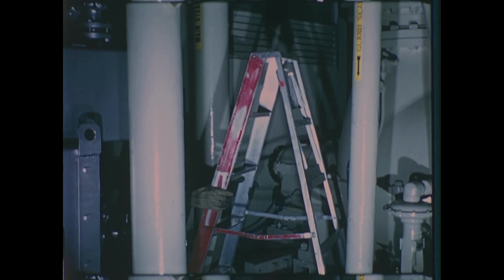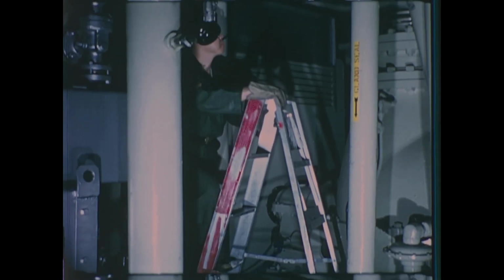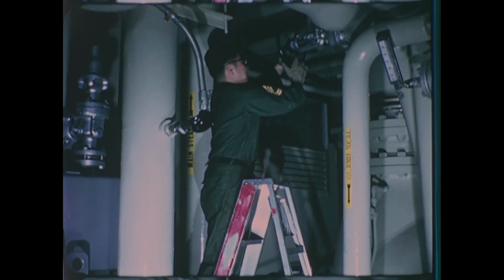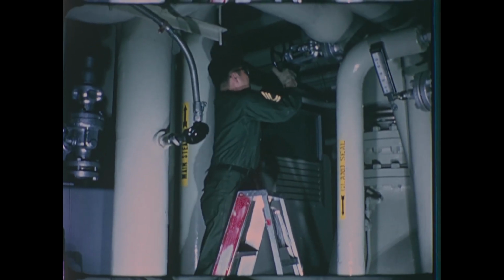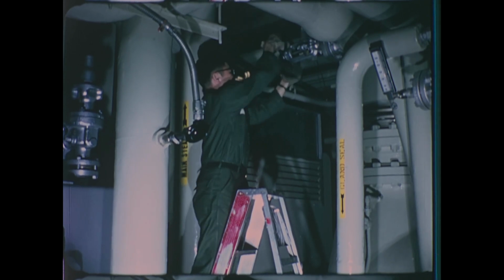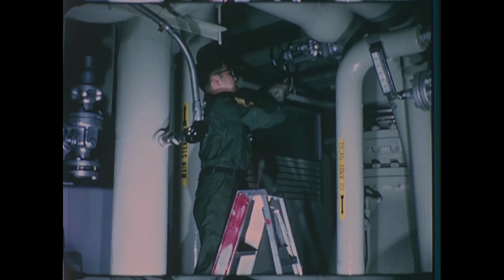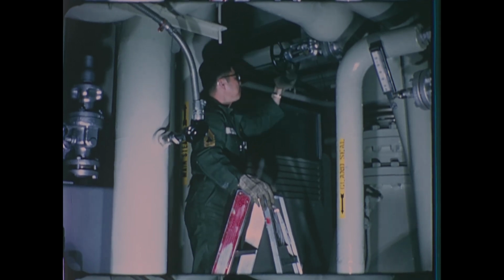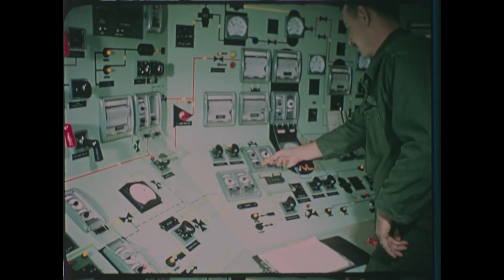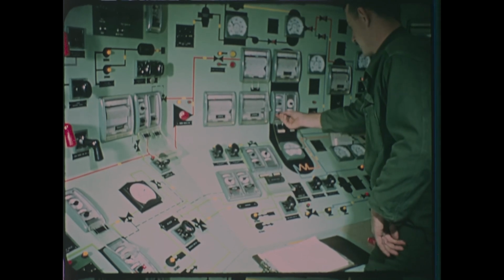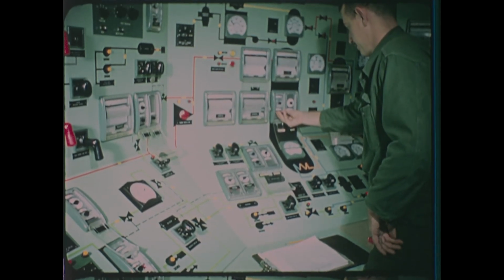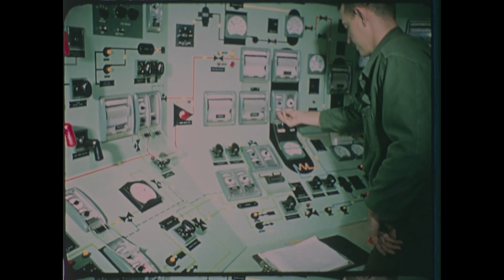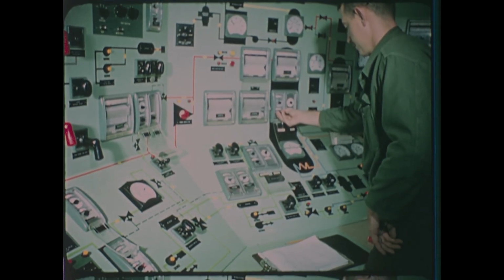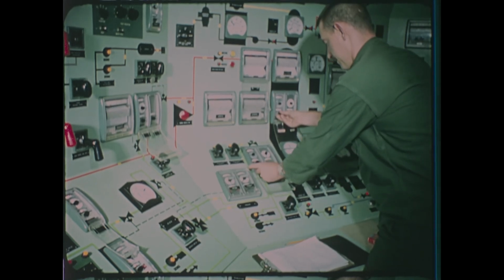Here, the equipment operator places the feed water heater in service by opening the valve from the turbine's first stage extraction system. At about 20,000 pounds of feed water flow, the console operator puts the controller in the automatic mode. He puts the feed water flow controller in manual balance and the steam generator level controller in manual. He adjusts the manual control of the steam generator level controller until the feed water flow controller deviation meter reads 0.